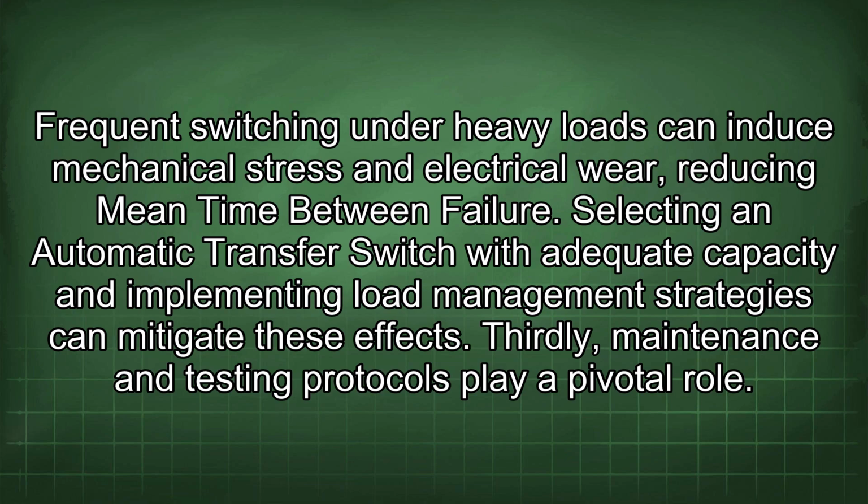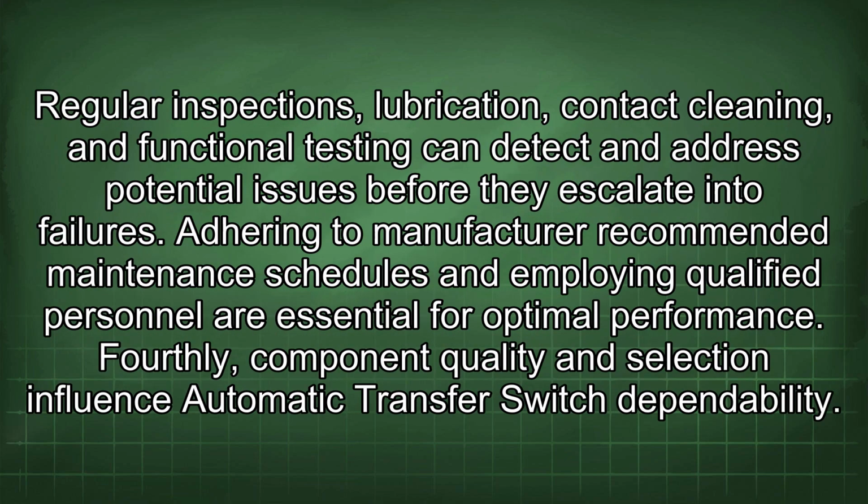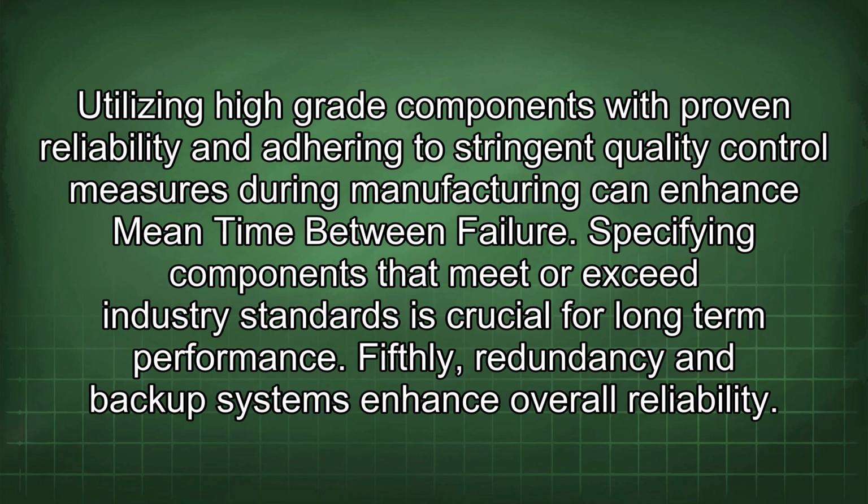Thirdly, maintenance and testing protocols play a pivotal role. Regular inspections, lubrication, contact cleaning, and functional testing can detect and address potential issues before they escalate into failures. Adhering to manufacturer-recommended maintenance schedules and employing qualified personnel are essential for optimal performance. Fourthly, component quality and selection influence automatic transfer switch dependability. Utilizing high-grade components with proven reliability and adhering to stringent quality control measures during manufacturing can enhance mean time between failure. Specifying components that meet or exceed industry standards is crucial for long-term performance.